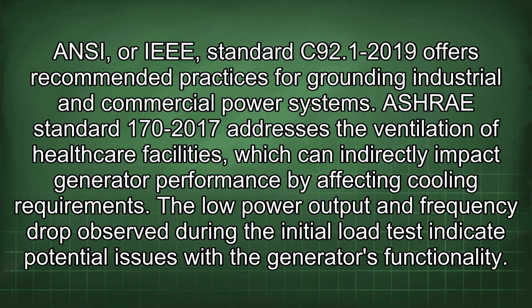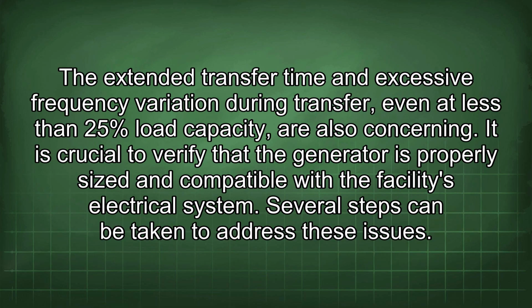The low power output and frequency drop observed during the initial load test indicate potential issues with the generator's functionality. The extended transfer time and excessive frequency variation during transfer, even at less than 25% load capacity, are also concerning. It is crucial to verify that the generator is properly sized and compatible with the facility's electrical system. Several steps can be taken to address these issues.